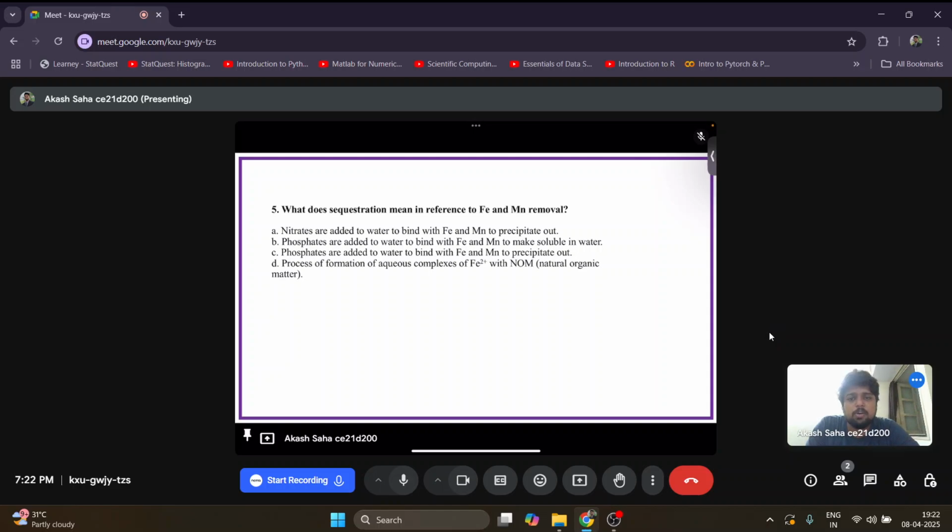Phosphates are added to water to bind the ferrous and manganese to precipitate out, or the process of formation of aqueous complexes of ferrous with NOM, that is the natural organic matter. So what do you mean by sequestration in ferrous and manganese removal? Just think about it.